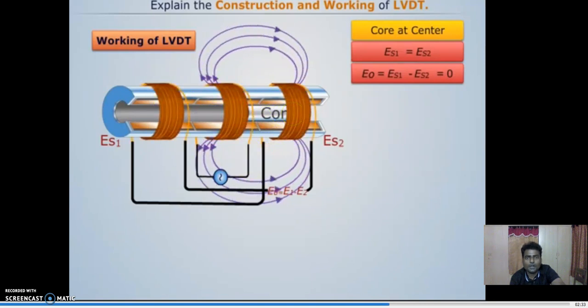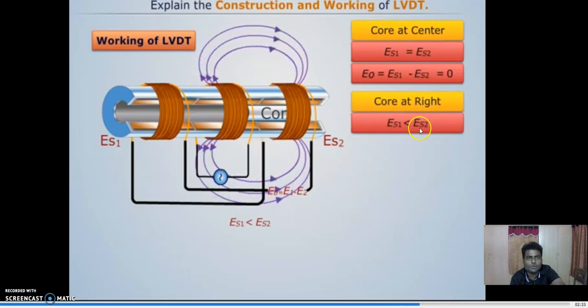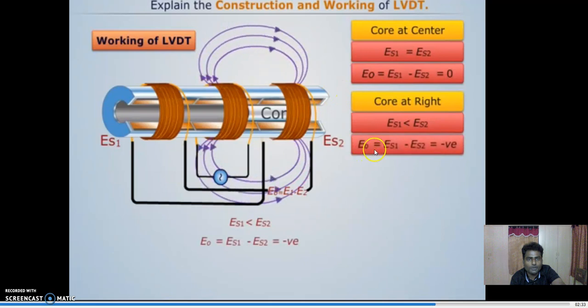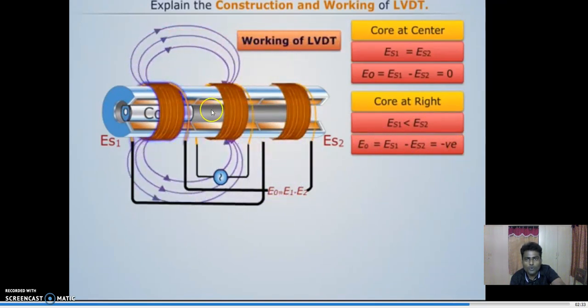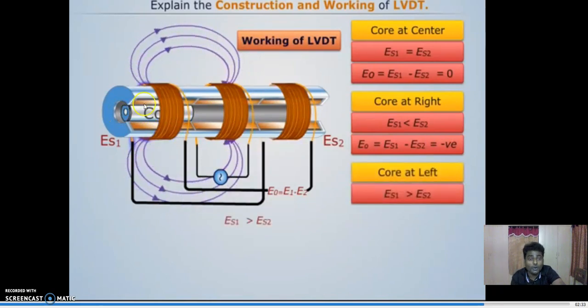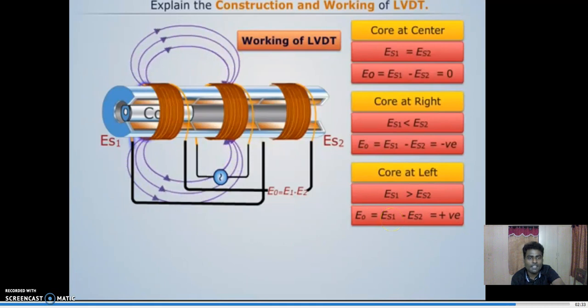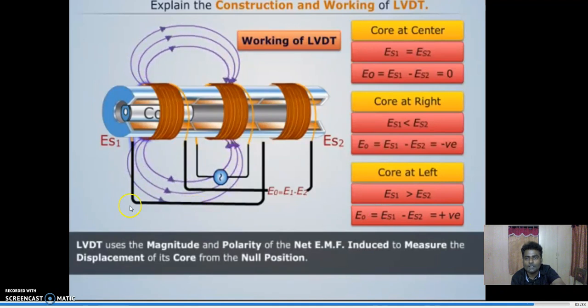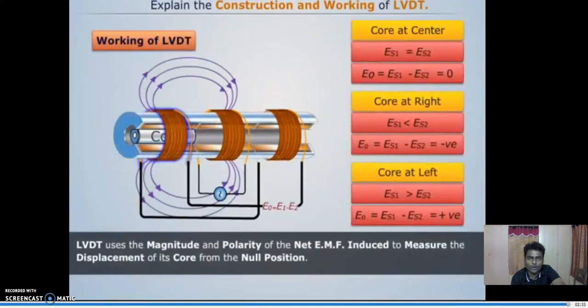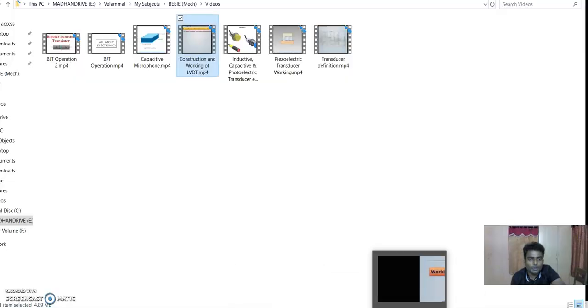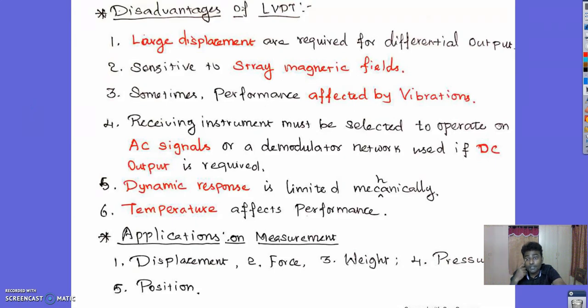When the core is moved towards the right side, ES2 becomes greater than ES1. When moved towards the left, ES1 becomes greater than ES2 and the output voltage ES1 − ES2 is positive. Thus, LVDT uses the magnitude and polarity of the net induced EMF to measure the displacement of its core from the null position. This video explains the construction and working of the LVDT.